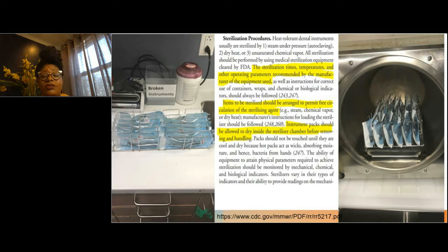So when you're going to prepare your pouches to be placed within the sterilizer, it's important that you also provide means for your pouches to have adequate spacing. And also you want to limit wet packs. You don't want to open up your sterilizer and see that all of your packs are wet, because that is an indicator that you have to reprocess everything.